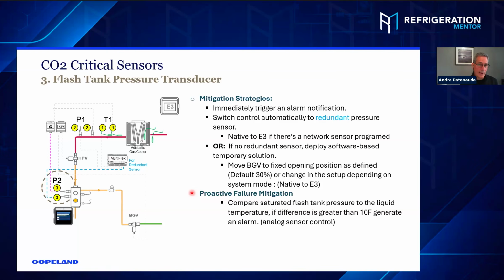Now, proactive, nothing's failed yet. What can give us maybe a heads up of a potential failure? You compare the saturated flash tank pressure to my liquid temperature. Should be pretty close, right? It is a saturated condition inside of a flash tank. So if you got more than 10 degrees, something's off. It's either the transducer or the temperature sensor. Get someone in to check it out before you get a call that the system's down. Okay.